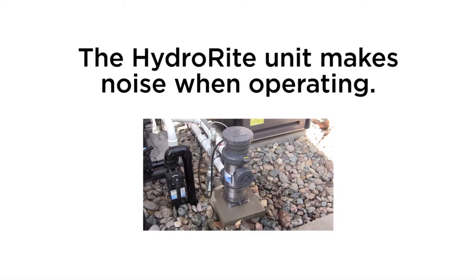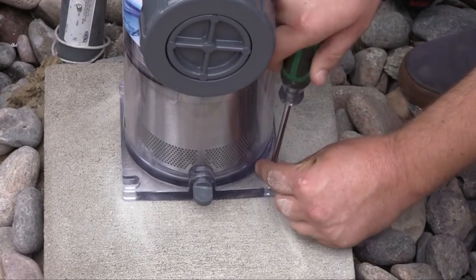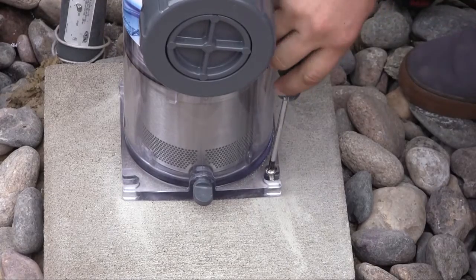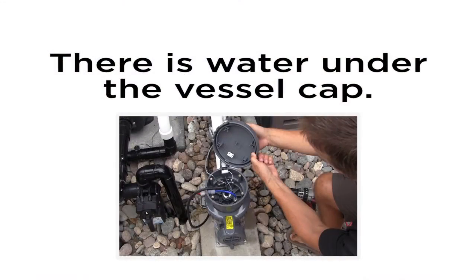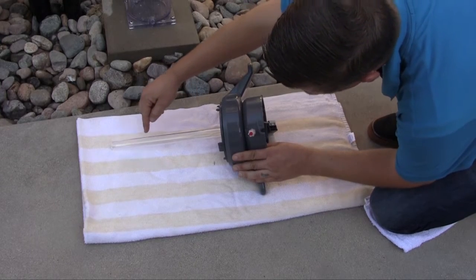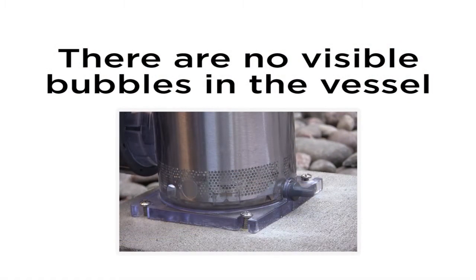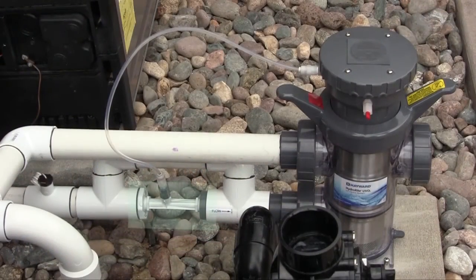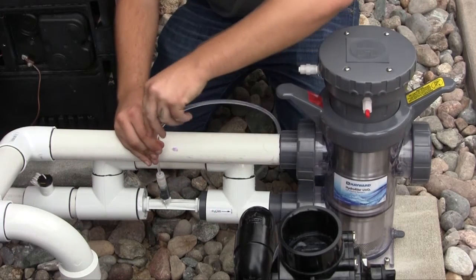If the HydroRite unit makes noise when operating, the vessel may not be properly attached to a firm mounting base, or the vessel bottom plate may be cracked or damaged. If there is water under the vessel cap, the quartz sleeve seal may be bad or there may be a broken or cracked quartz sleeve. If there are no visible bubbles in the vessel, note that bubbles are normally an indication that ozone is being generated. The flow rate through the venturi may be too low — below 35 gallons per minute — or the venturi tube may not be properly installed or seated.